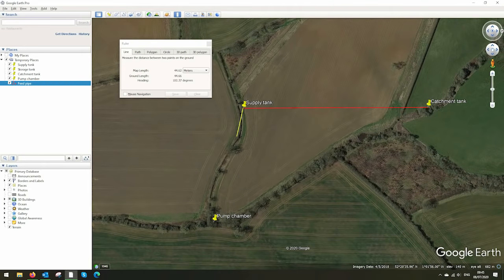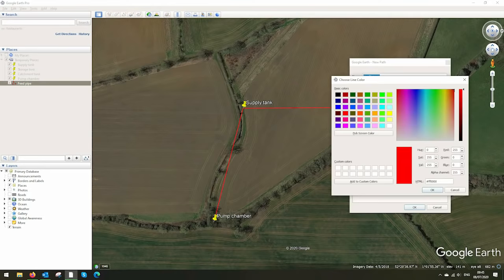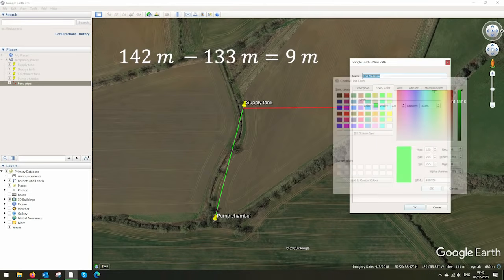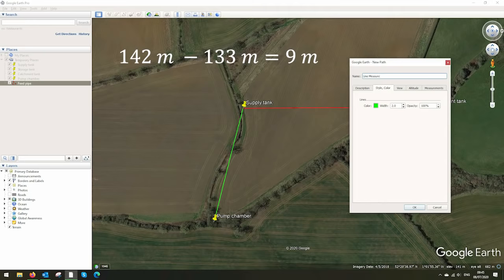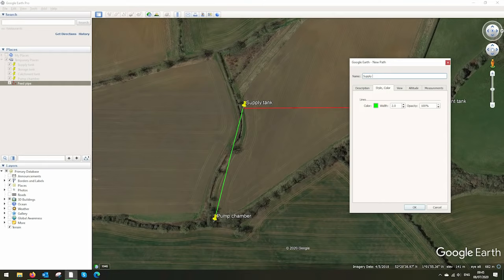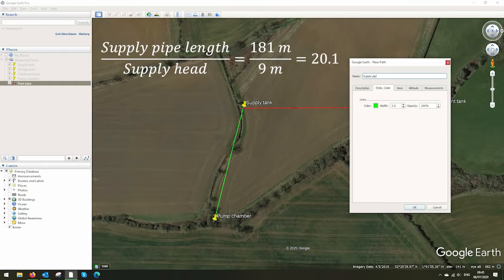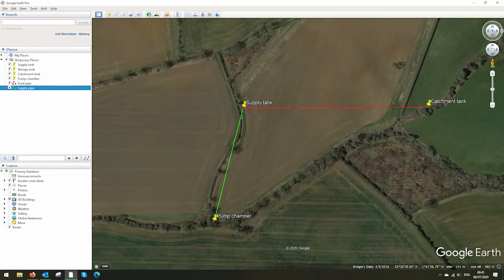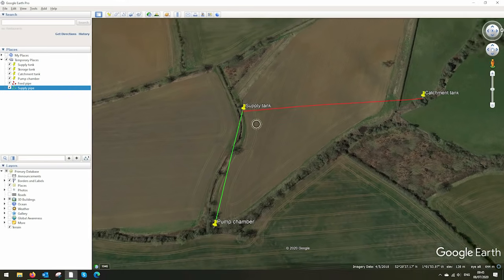That's the feed pipe and now we'll put in the supply pipe. We're taking the pump chamber elevation away from the supply tank elevation and we know that we have nine meters of head. Dividing the supply pipe length by this gives a gradient of about 1 in 20, which is not ideal, so we need to shorten this supply pipe.